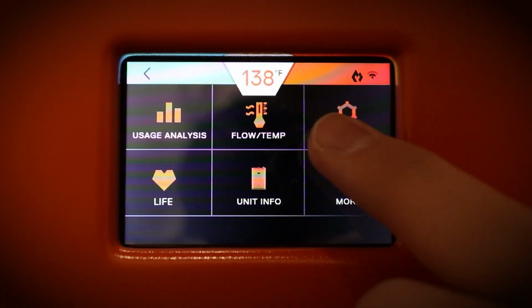To enter combustion mode, the unit will need to operate at its maximum firing rate. We will achieve this by increasing the demand on the heat exchanger. Please do the following. Calculate the difference in temperature between the unit's set point and the incoming water temperature. This is our temperature delta. Multiplying this temperature delta with the flow rate through the unit and multiplying that product by 500 will give you the load in BTU per hour.